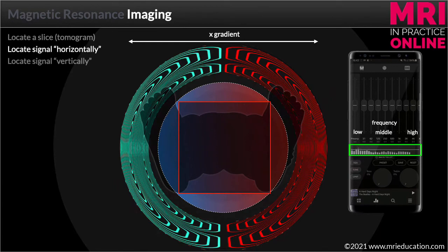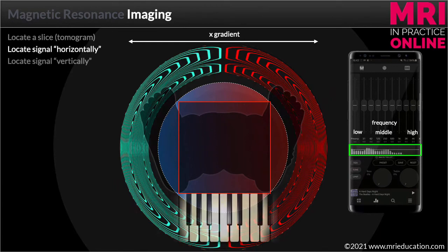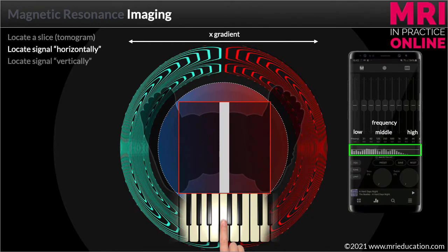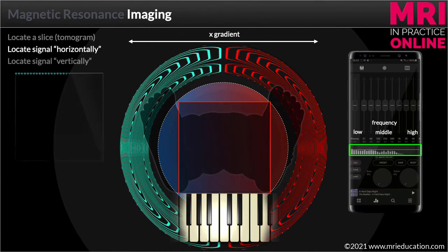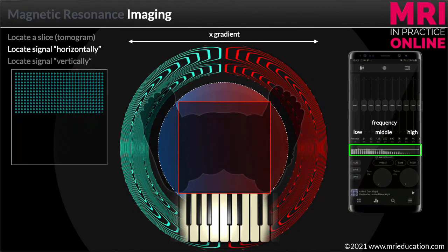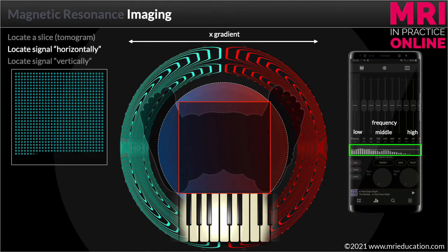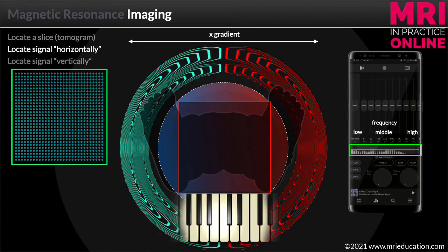Higher frequencies are to the patient's left and lower frequencies to the right. During an MRI acquisition we collect the signal repeatedly — perhaps 256 or 512 times. As we collect the signal each time, we sample the signal amplitude, taking little snapshot measurements as the signal is collected by the receiver coil, with 256 or perhaps 512 measurements taken each time. This results in a grid of data. To keep it simple, this grid has just 30 rows, each representing one signal collection, and each row has 30 sampling points shown as little blue dots.